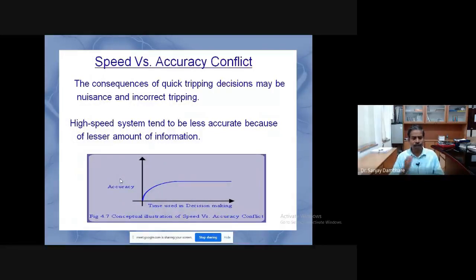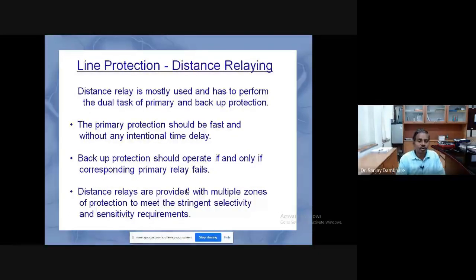So this speed versus accuracy is a very famous conflict, and a proper engineering decision has to be taken, because if you reduce the time, then your accuracy may be compromised. It doesn't mean that if you increase the time excessively, you will get more accuracy. No, that is also not correct. So for transmission line protection in power systems, we mainly go for distance protection, and the distance relay is most commonly used because it performs both tasks, primary as well as backup. The primary protection should be as fast as possible without any intentional delay, and backup protection should be responsible for providing protection if primary protection fails, right?